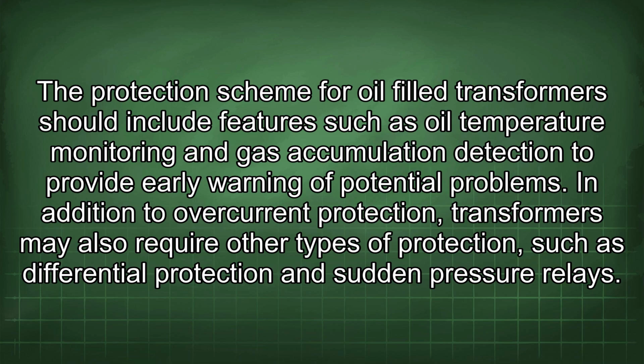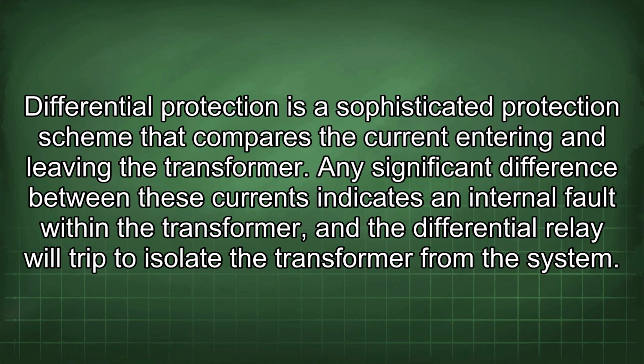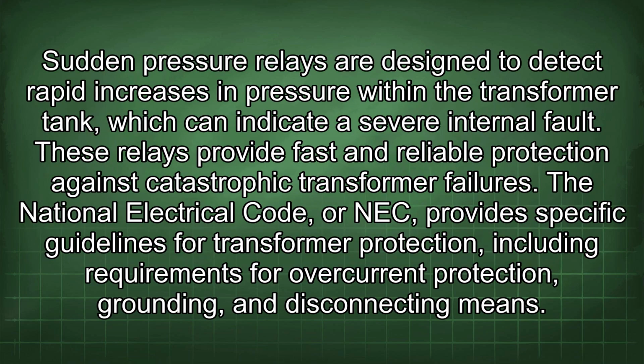In addition to overcurrent protection, transformers may also require other types of protection, such as differential protection and sudden pressure relays. Differential protection is a sophisticated protection scheme that compares the current entering and leaving the transformer. Any significant difference between these currents indicates an internal fault within the transformer, and the differential relay will trip to isolate the transformer from the system. Sudden pressure relays are designed to detect rapid increases in pressure within the transformer tank, which can indicate a severe internal fault. These relays provide fast and reliable protection against catastrophic transformer failures.